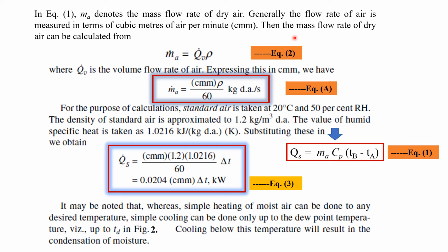So now the mass flow rate of dry air can be calculated from equation number 2. The mass flow rate of the dry air is expressed as the volumetric flow rate multiplied by the density, where Qv is the volumetric flow rate of air. We can express this volumetric flow rate in CMM, which stands for cubic meters per minute. So we have equation 2 modified in this fashion: ma dot is going to be expressed as CMM divided by 60 multiplied by rho. The units are going to be kg of dry air per second. Let it be my equation number A.